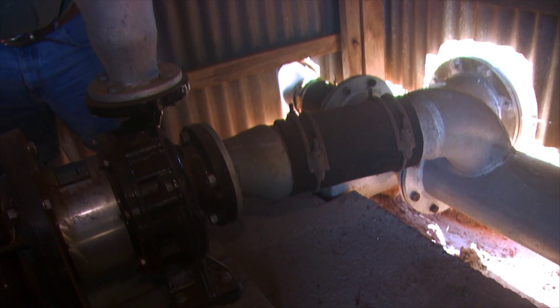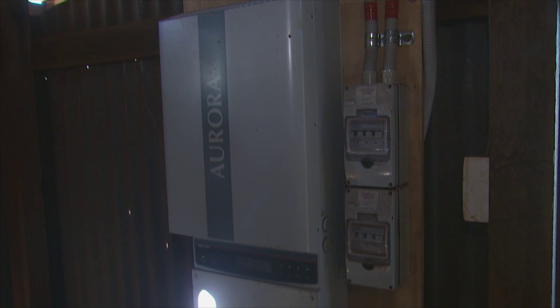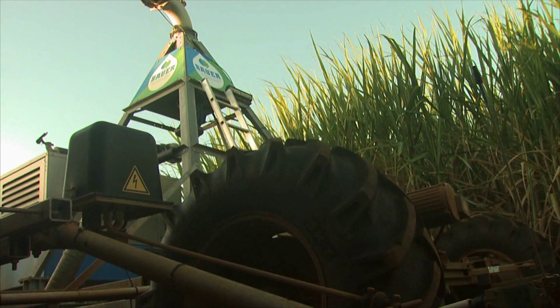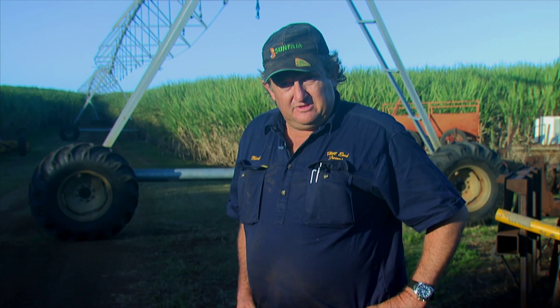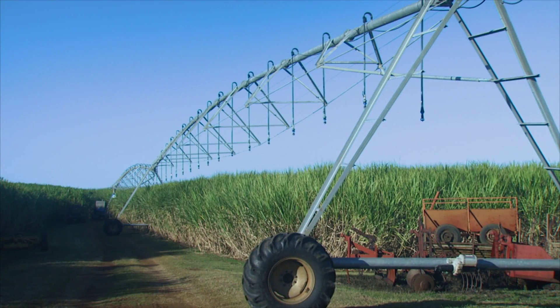This pump is pumping 52 litres a second, as against approximately 26 or 27 litres for the two previous pumping systems. Mark and Brian also have a five-kilowatt solar power system installed at this pump site, which is also impacting on power costs. The pumping infrastructure that was there was probably 40 years old — fairly antiquated and probably never very efficient even when new. Friction loss is a major energy consumer in irrigation. The existing underground line was only a 150-millimetre pipe; we've gone to 200 millimetre, and the friction loss is just under half what it was.